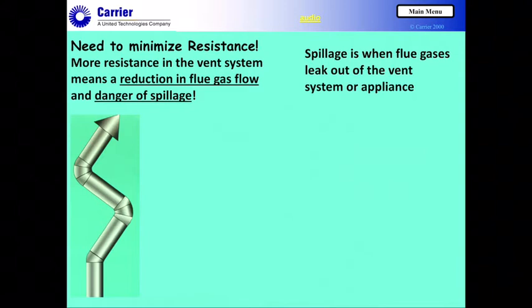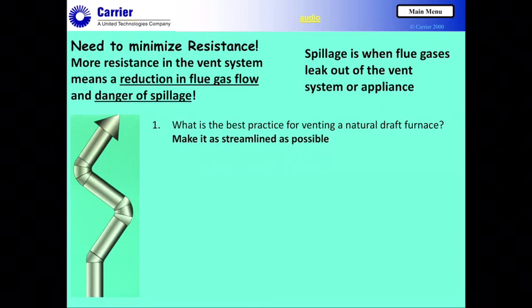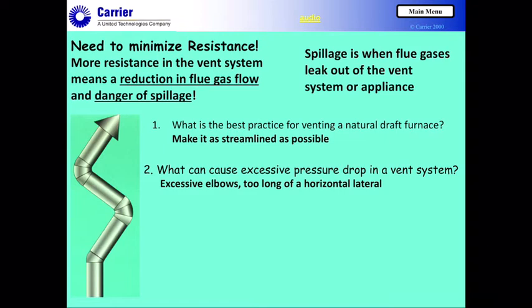One key need is to minimize resistance. More resistance in the vent system means reduced flue gas flow and makes venting more difficult, which also creates a problem with spillage. Spillage is when flue gases leak out of the vent system or appliance and back into the building. Best practice for a natural draft venting system is to make it as streamlined and low-resistance as possible. Excessive pressure drop can come from too many elbows, too long a run, and especially horizontal laterals — even if pitched upward, going horizontally makes venting more difficult.